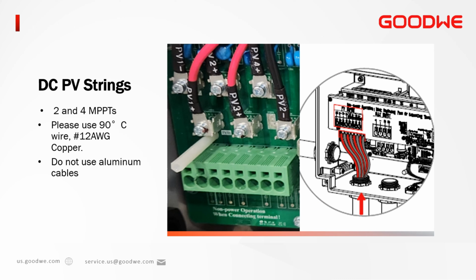This is one of the major differences between AES and ABP. Because ABP is AC coupled, it will not have an array connection. These instructions are only for AES. Before starting the array connection, make sure the DC switch is in the off position. You are connecting each string directly to the inverter. There are no fuses. The two smaller versions, the 5 and the 6, have 2 MPPTs, and the rest of the larger inverters have 4. We recommend a number 12 gauge copper for the positive and negative conductors.